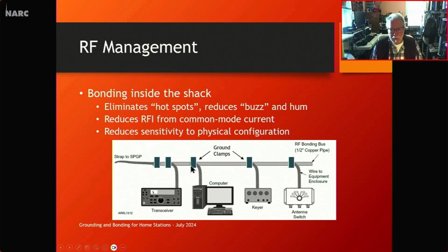If you do use copper pipe, use a ground clamp, because it's designed to maintain pressure between two metal components, whether they're wires or pipes or rods or whatever. If you use the little stainless steel hose clamps that you screw on and tighten up, those are not designed for metal to metal contact - that's designed for metal on one hand and some kind of flexible material like rubber. Well, it's a hose clamp, right?